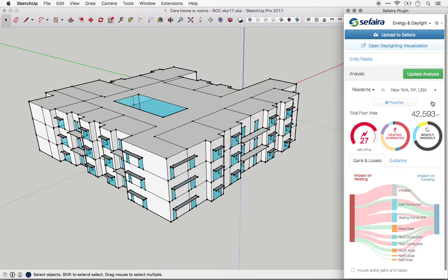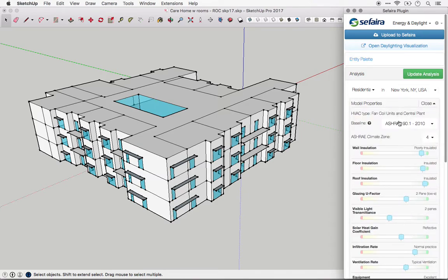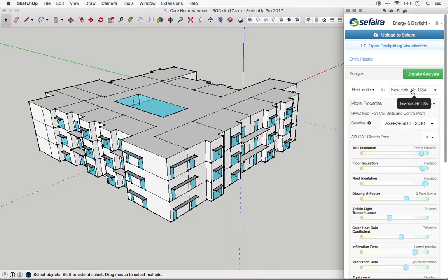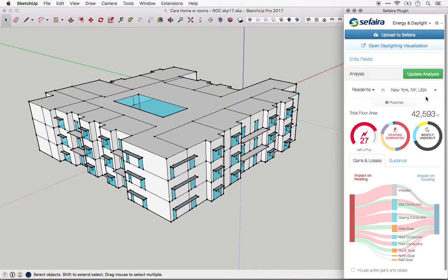The second input is the location. Based on the location that you enter, Sefaira automatically selects the nearest EPW weather file for the analysis, and that's used for both the energy analysis and for annual daylighting metrics, which are location-specific. If you're using an ASHRAE baseline, then the location also automatically changes the climate zone to the appropriate one. I should mention, if you have a custom weather file that you'd like to use, that's something that you can do in the web application.